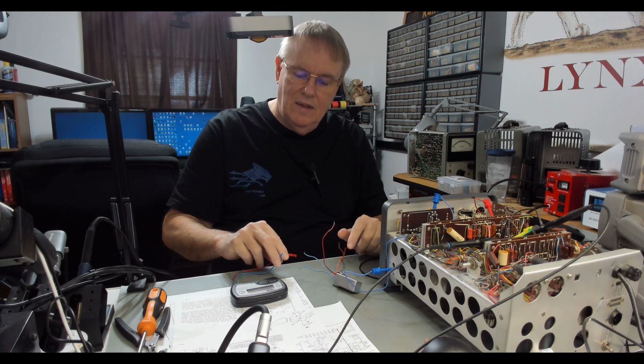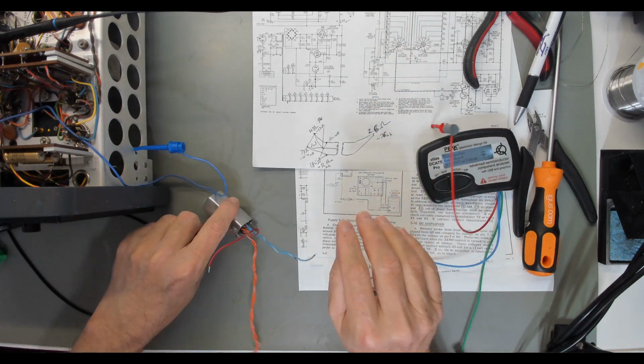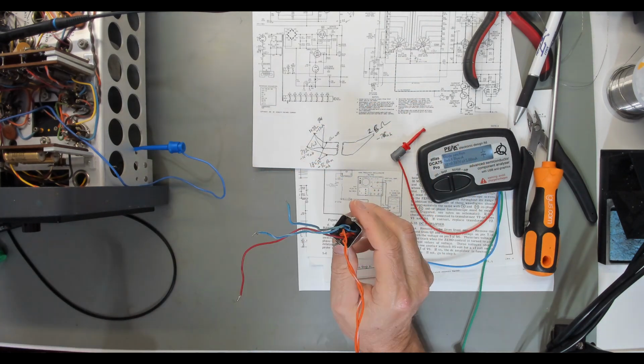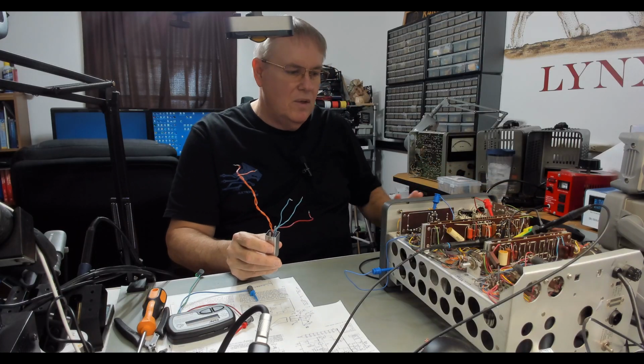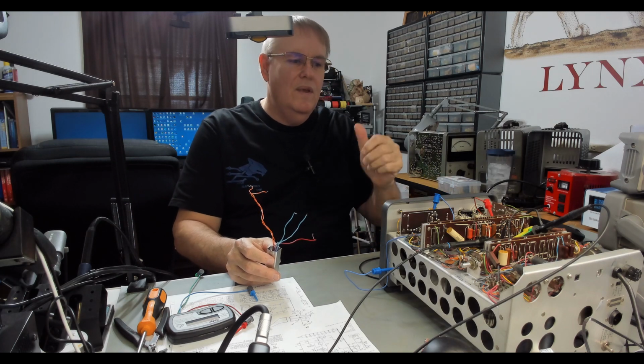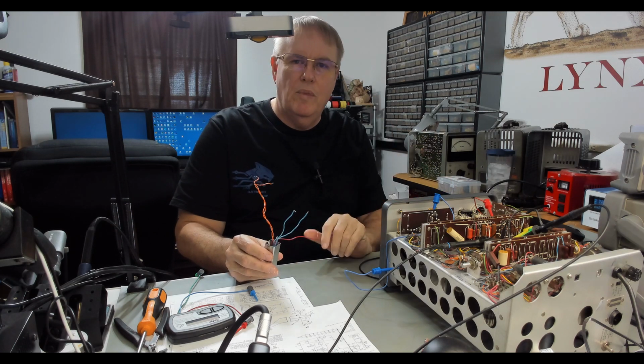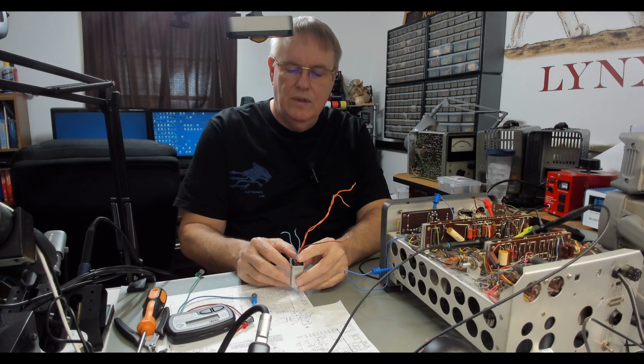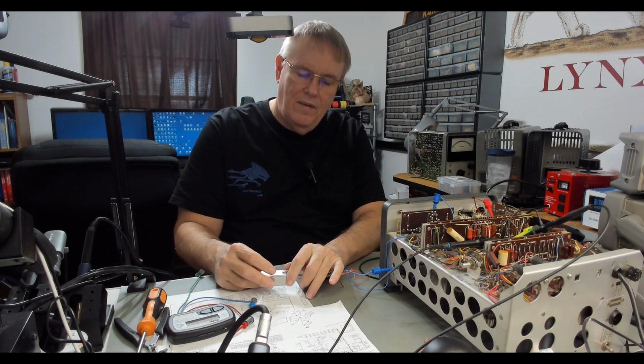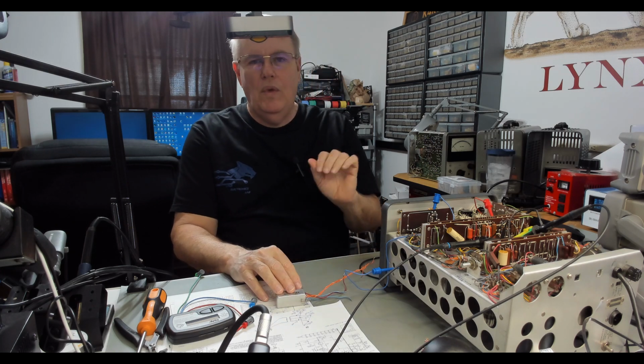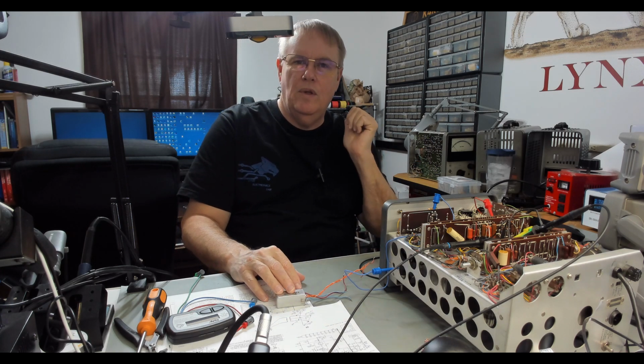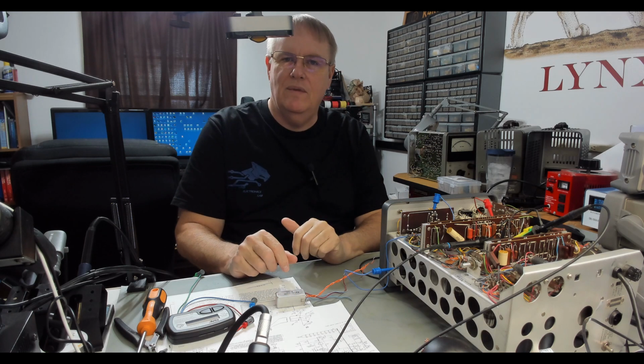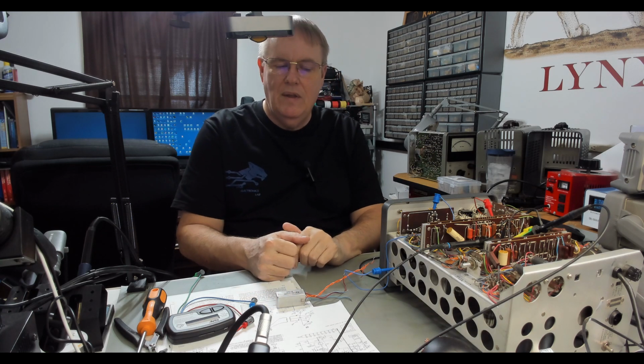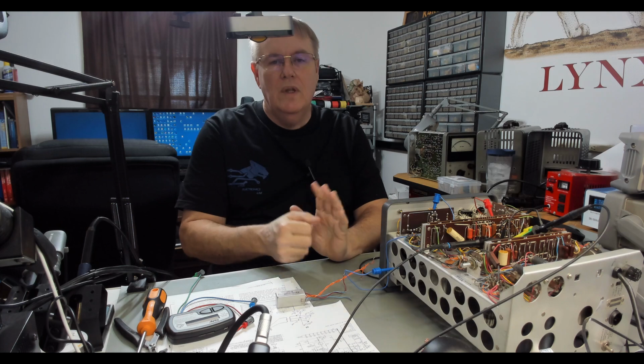I'm thinking in this can, and the thing about it is, if we take a good look in there, it's potted. Don't know where I get one of these without buying another meter. I'm not buying another meter. The other meter is a much newer meter, does not use this transformer. So that's where I'm at. If I can't get anywhere with this, I'll pull this one off the bench. I'll put the other one on the bench, start working through it, and see if I can get it up and running. So that's the one that came with this probe. So anyway, that's where we're at.